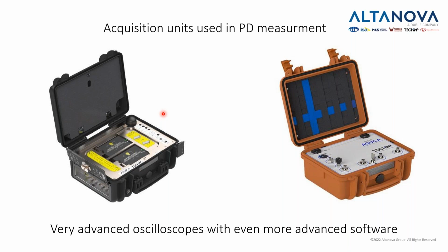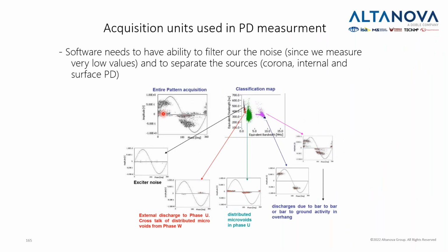There are some additional sensors which we will show, but what is important is that after you have done testing, it is very important that you must remove the noise. Since you are measuring very, very small values, the devices used in this measurement are very, very sensitive. Because of this sensitivity, the noise can mess up the measurement. So with our technology, you can easily remove the noise and separate the sources to understand what we are talking about, because this is one of those measurements where the execution of the measurement and obtaining of the results is not so difficult, but interpretation can be tricky if you don't know what you are looking at.